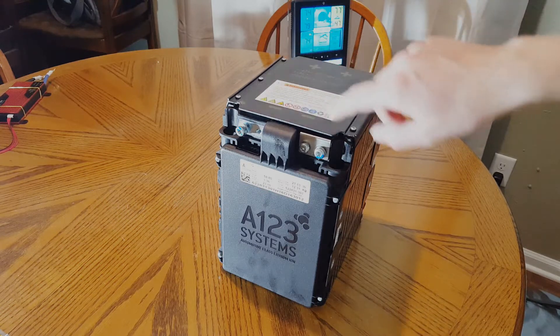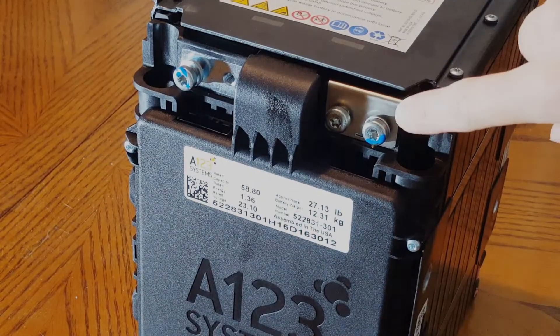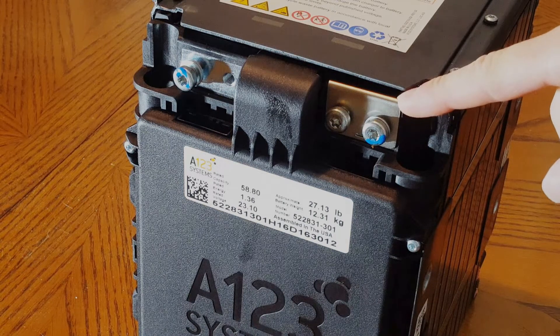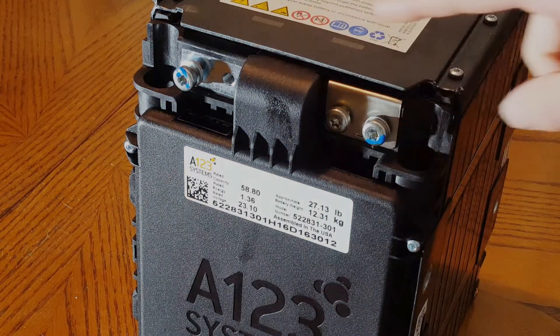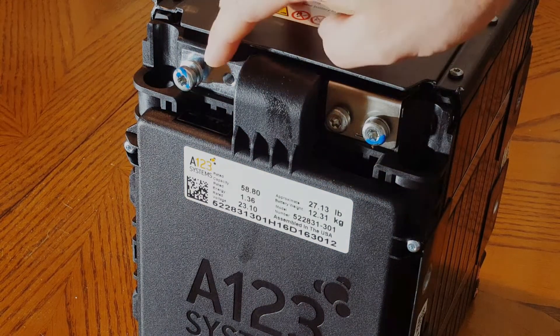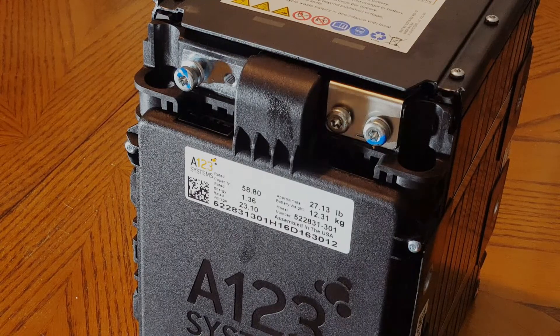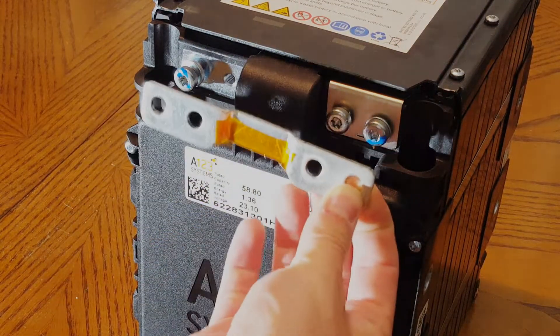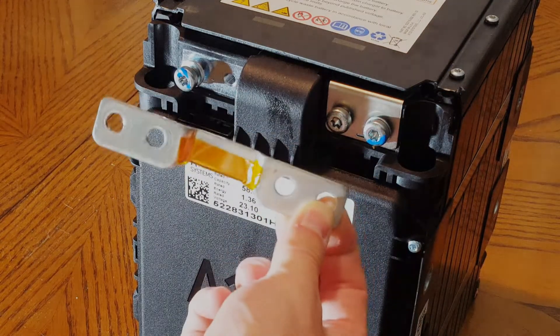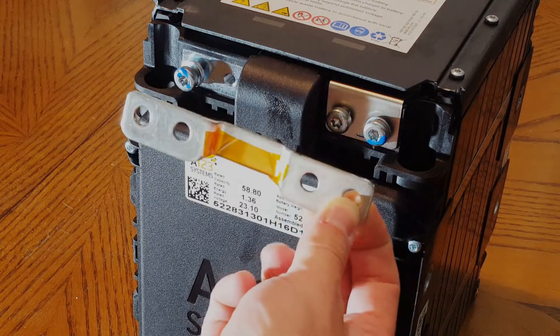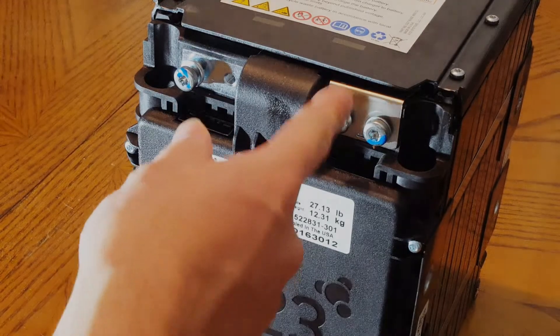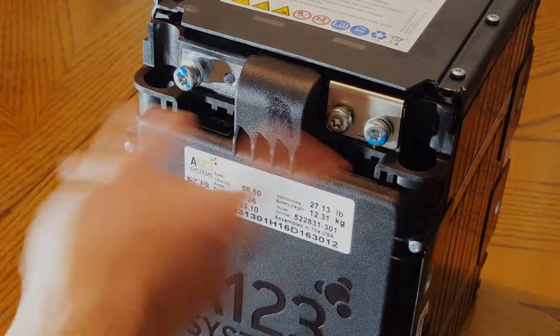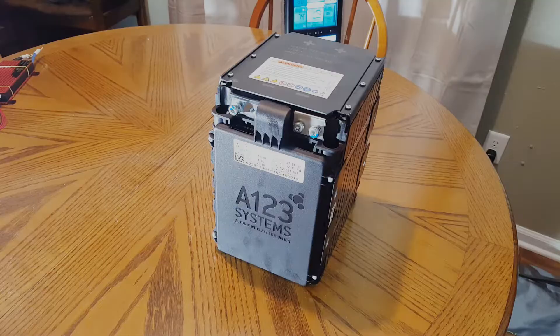You can see that this right one has this tab that wraps around the top, and the left one doesn't. So the left terminal is actually a dummy terminal and is only live if you use one of these bus bars. Some of these batteries had this on here, some of them didn't. But as it stands, this is live, this is not. So you need something to connect them.